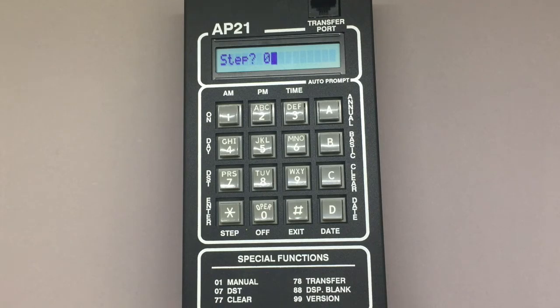However, the AP21 does not ship with the pulse feature activated, so that's something you'll have to do manually. If your application requires the relays to be on for more than 99 seconds, like in a school zone flasher environment, you'll need to program a step that turns off the relay after a desired amount of time.